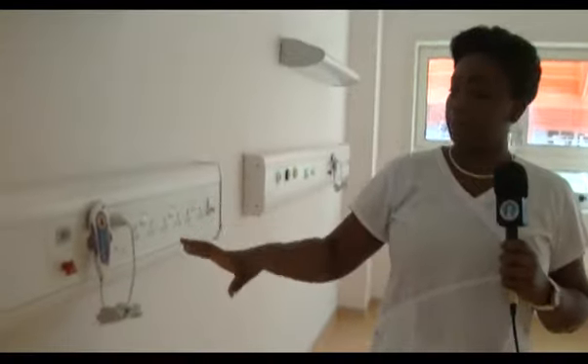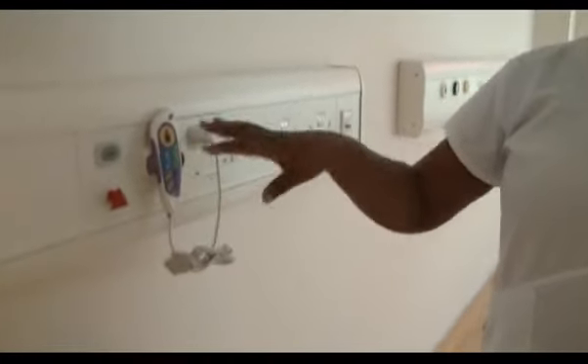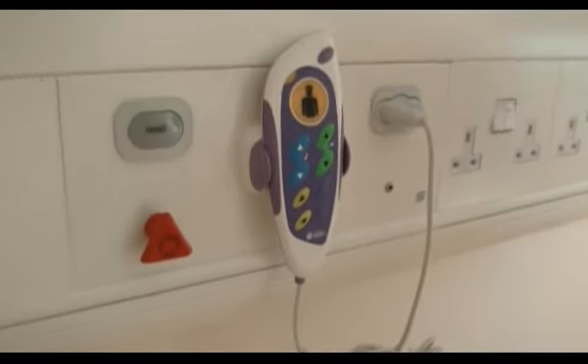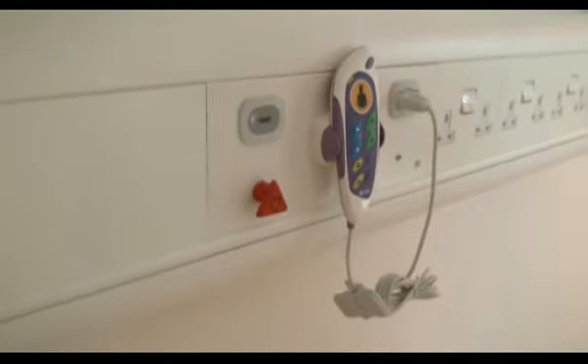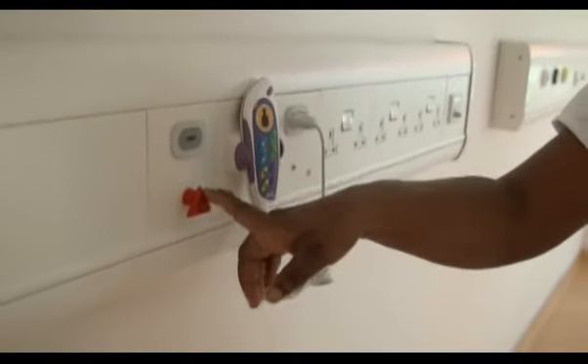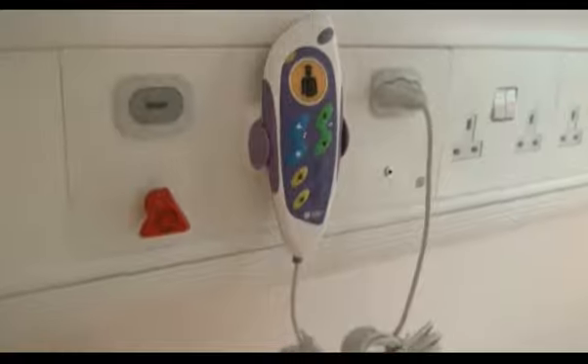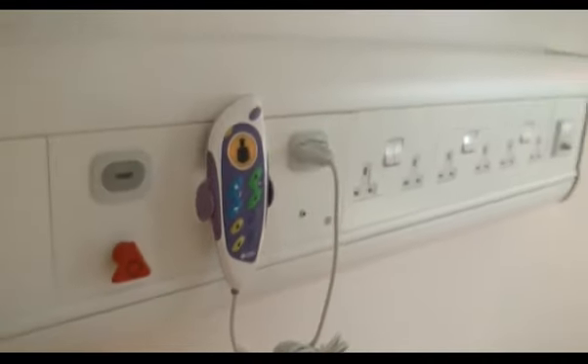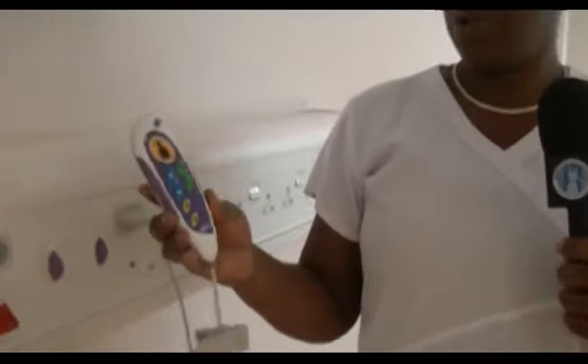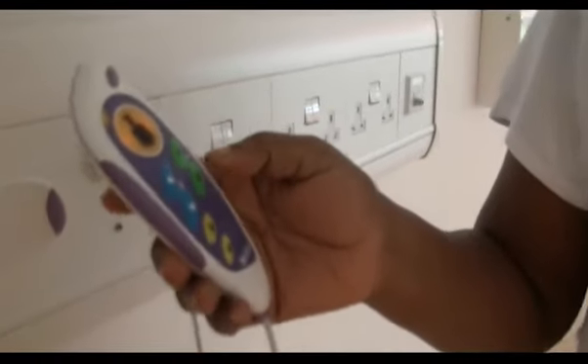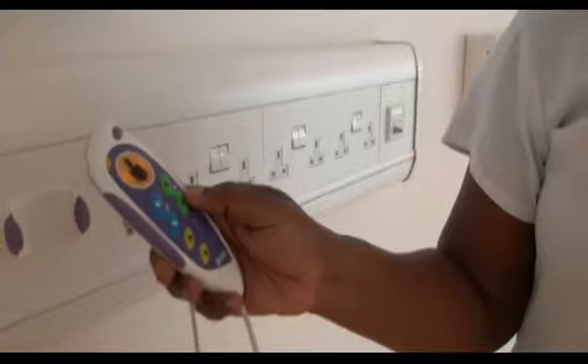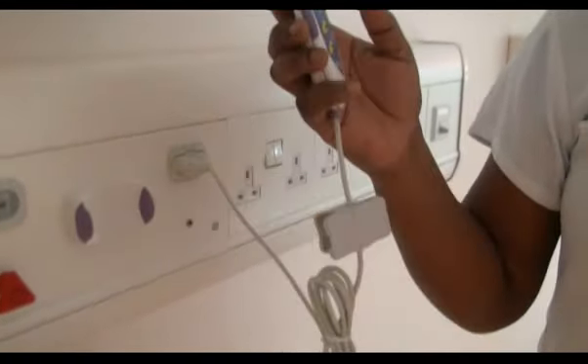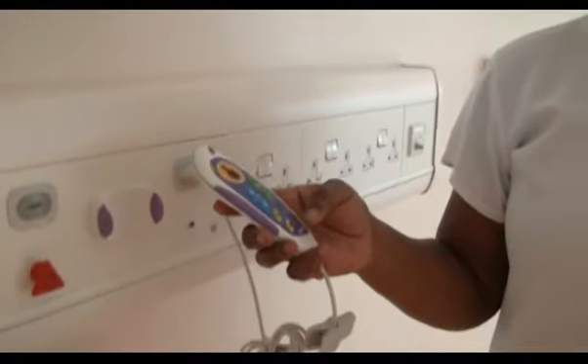We have the emergency setting and the nurse-patient call setting. In case of an emergency, the nurse or the patient can pull this button, and it will alarm. When it alarms, anywhere on the unit, the nurse will be alerted that there is an emergency. I will be demonstrating in a little while. This one is for the patient call system. It also controls a radio service and music. This is for the music, this is for radio. This is for the lights also, to brighten up the light in the night or to dim it, if they want to read or do anything with the child.